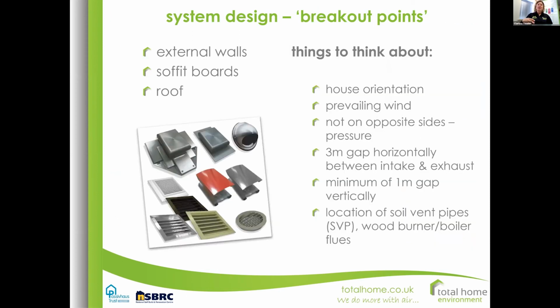Breakout points, where your fresh air in and stale air are going to be coming out. Normally these are in end elevations or soffit boards or the roof. You just have to watch house orientation, because we don't want to be getting the fresh air in from the south side, and if there's any prevailing winds, that could cause some whistling to go through the house. And you certainly wouldn't put an extract on one side and fresh air on one side and the exhaust on another, because you'll get different pressures going on.